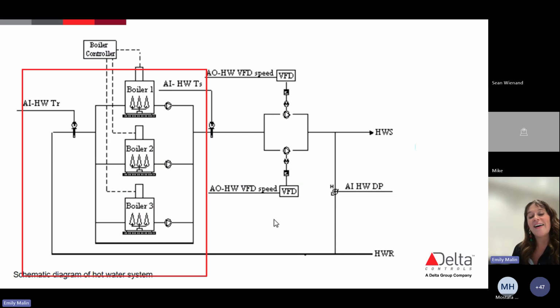I want lunch too. Anyways, okay, so we're looking at that first part here, and that's where we're actually going to look into the boilers. Our boilers are going to burn fuel in order to heat up that water. Throughout all of these, we're going to have that sensor network, right? That's going to monitor the temperature both inside the boiler as well as exiting the boiler. If that water isn't hot enough, the control system is going to send a signal to open a gas valve. Right? This is what's going to start to heat up that water more. You can also here have an igniter, which is going to light that burner to heat it up more. So those are the two ways of how that water is actually being heated up.